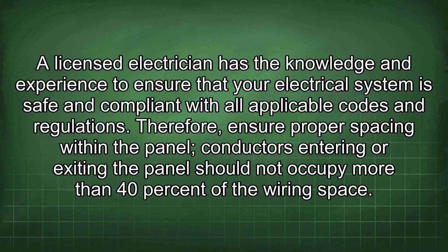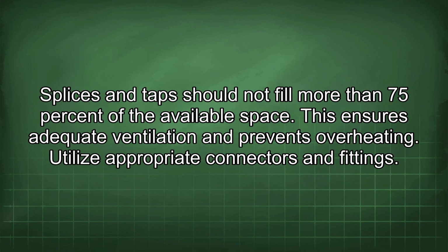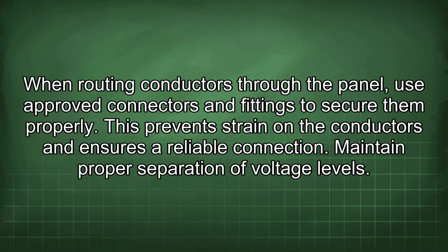Conductors entering or exiting the panel should not occupy more than 40% of the wiring space. Splices and taps should not fill more than 75% of the available space. This ensures adequate ventilation and prevents overheating. Utilize appropriate connectors and fittings. When routing conductors through the panel, use approved connectors and fittings to secure them properly. This prevents strain on the conductors and ensures a reliable connection.